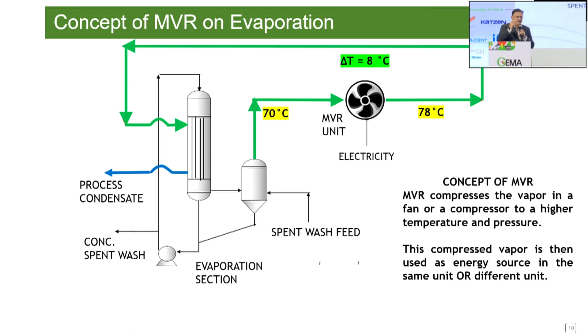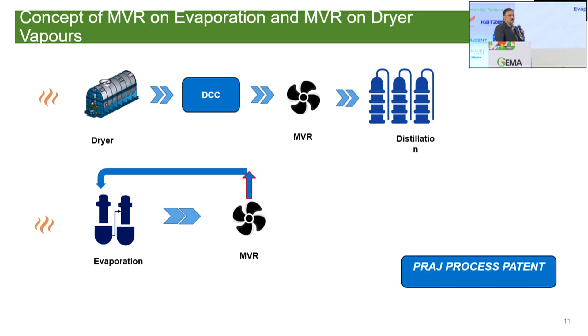The next stage is using MVR in the evaporation section, but also in addition, using MVR on the drier vapors. So you have the dryer, take the vapors to a direct contact condenser, pass it through MVR, and then those vapors can be used in the distillation section as heat input. Here, what you're achieving is a steam consumption of about 2.3 kg per liter, a further reduction in steam consumption.